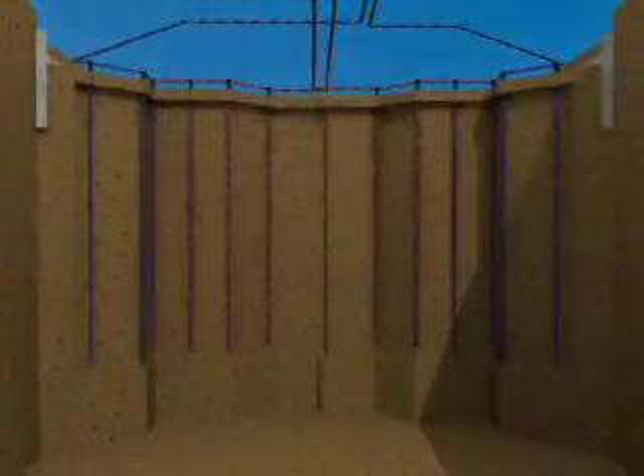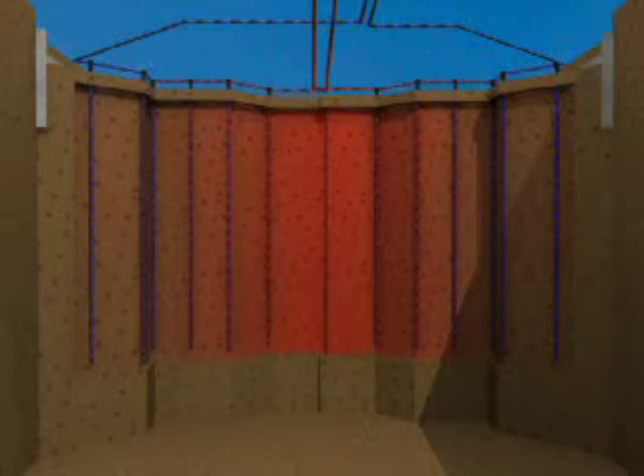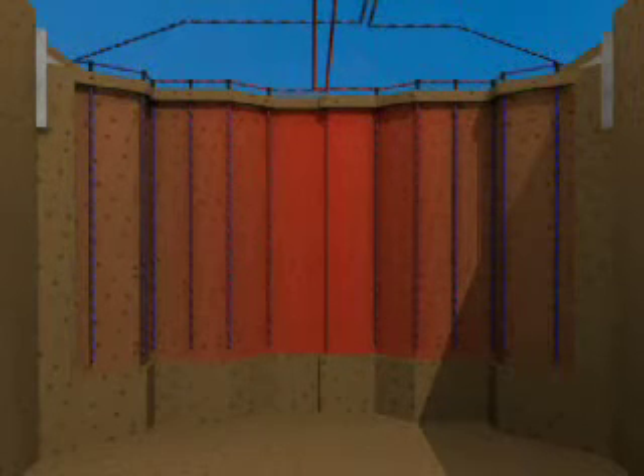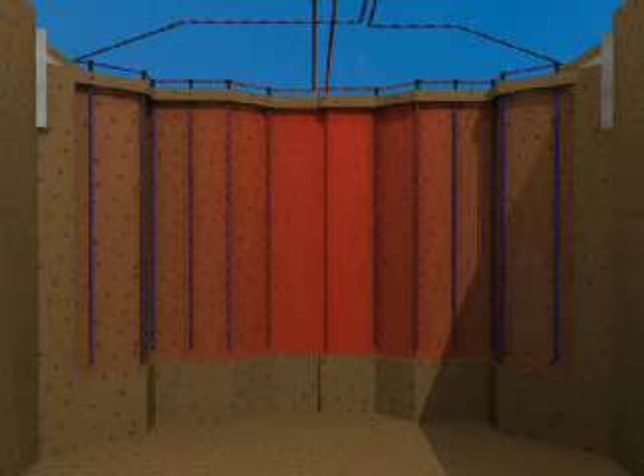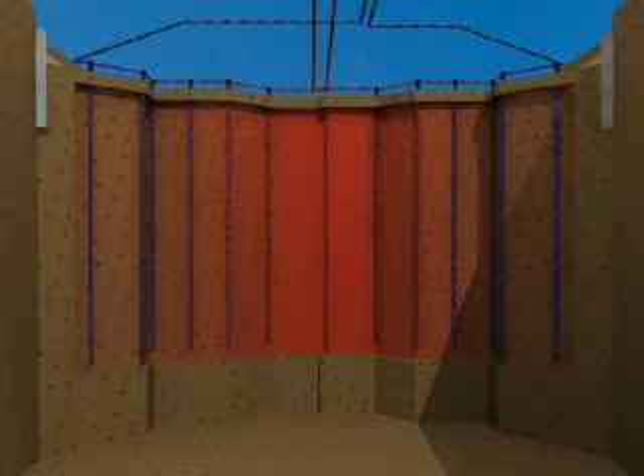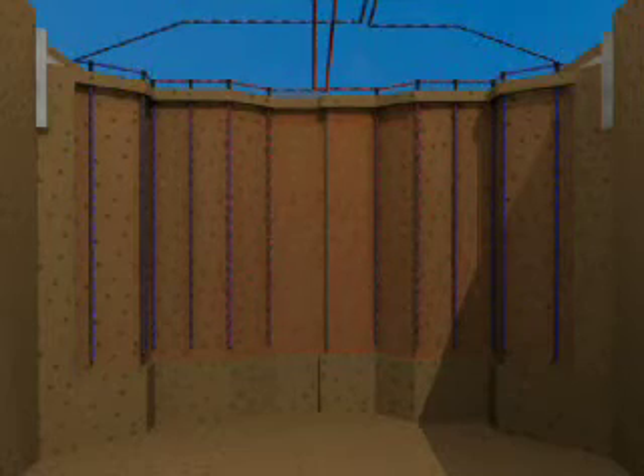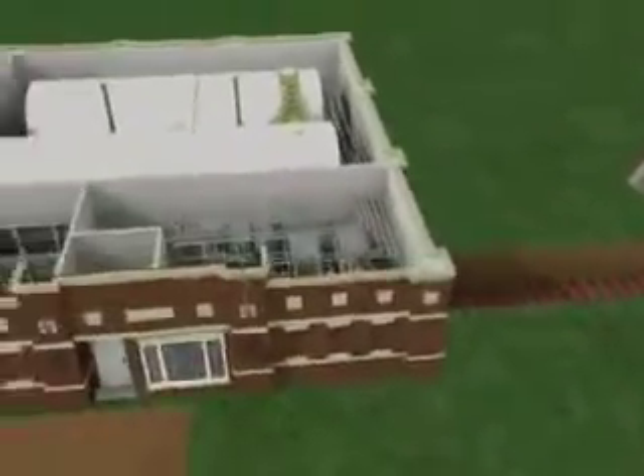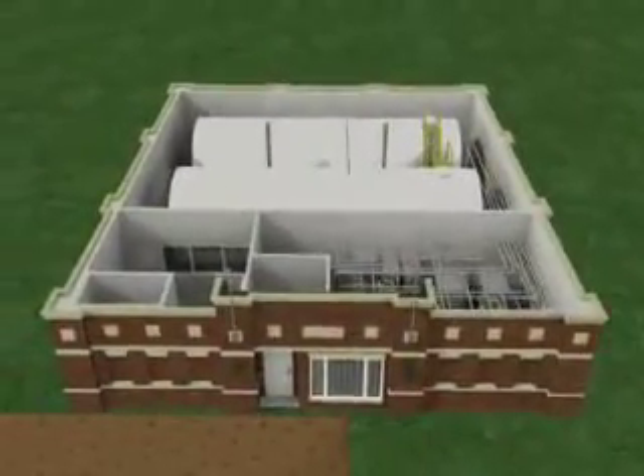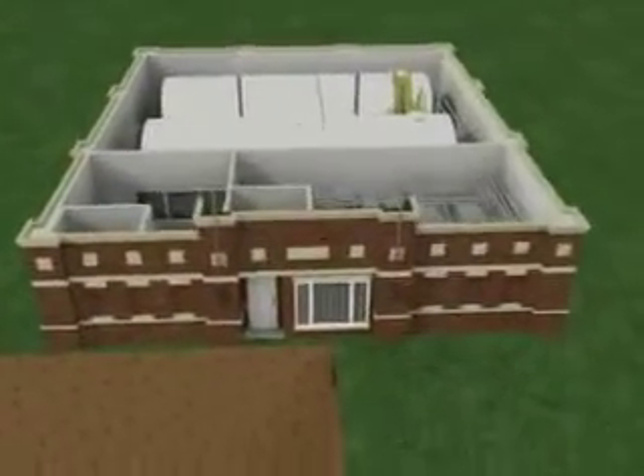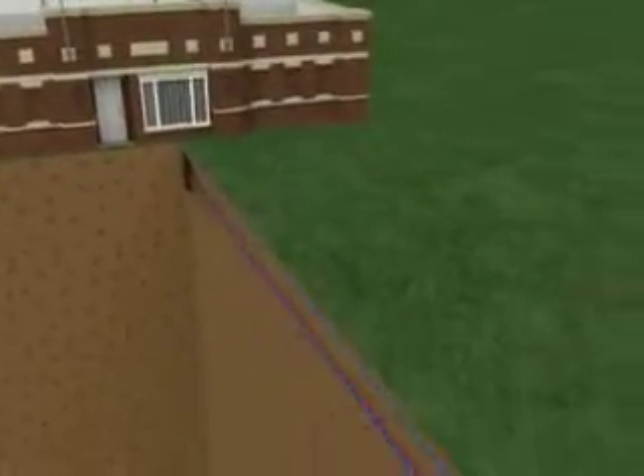To improve the insulation properties of the earth and keep the heat in, the borehole system is covered with sand, high-density R40 insulation, a waterproof membrane, clay, and other landscaping materials. The water completes its circuit of the borehole system and returns to the short-term storage tanks in the energy center to be heated again and repeat the same process. When winter arrives and heat is needed for the community, the heat in the borehole system is distributed by water back to the energy center and then through the district heating loop to each home.